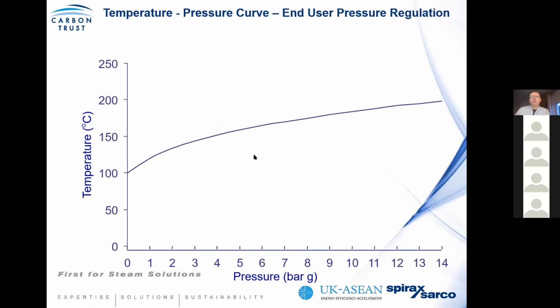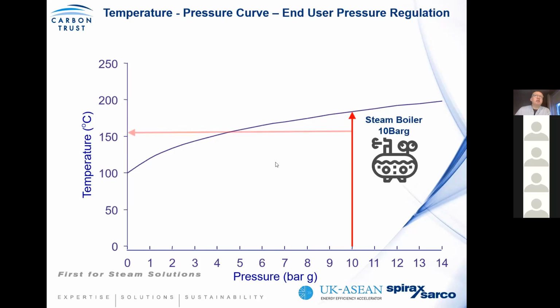However, what we need to consider is that although we advocate generating at the highest possible pressure and distributing at the highest acceptable pressure, end users operate to certain temperatures. Within your very process, you're most likely controlling to a temperature. However, if we take our 10 bar boiler and look at this profile, what we can see is that at 10 bar, according to the steam tables, you're at about 185 degrees, a temperature which is often too hot for certain processes and may cause product spoilage.